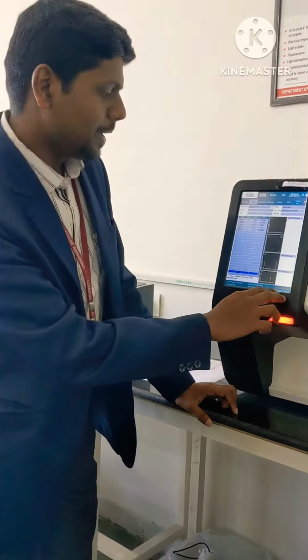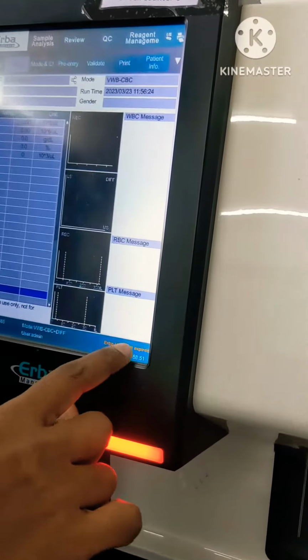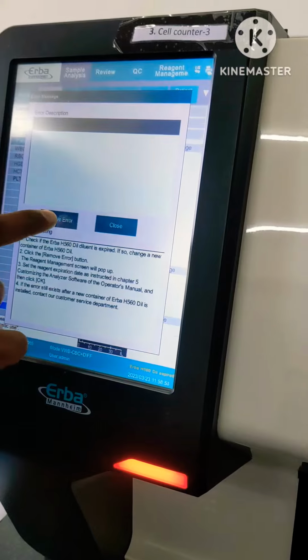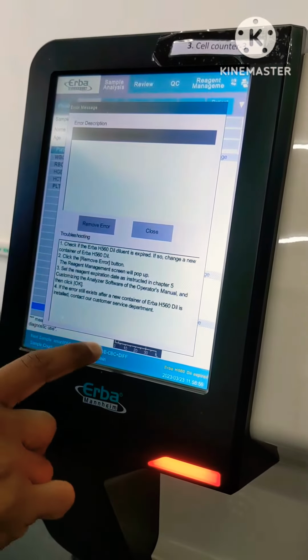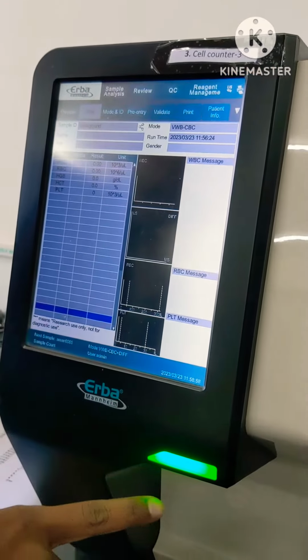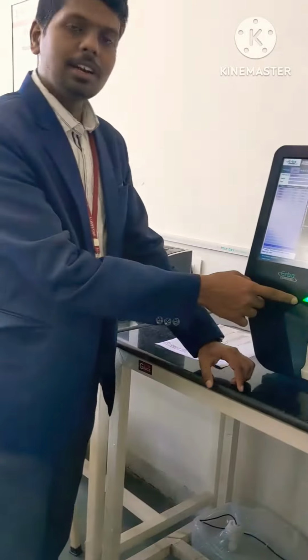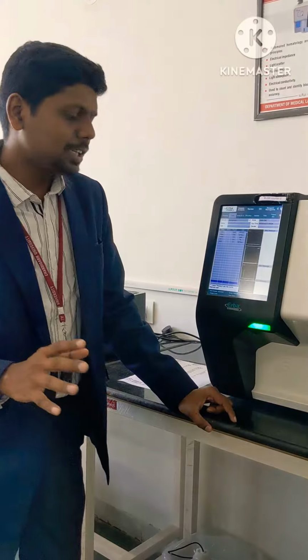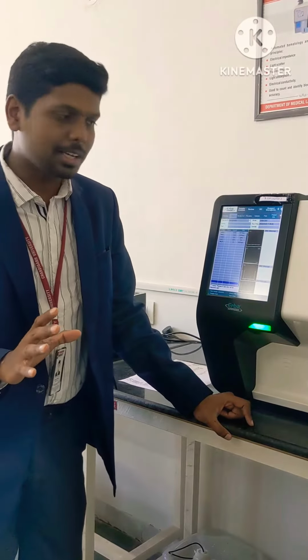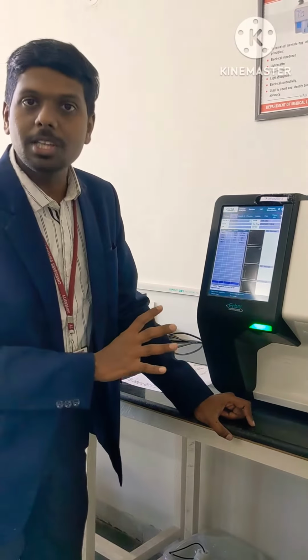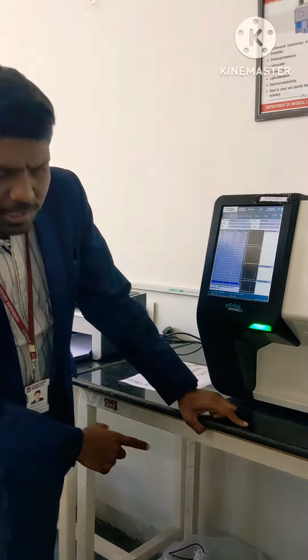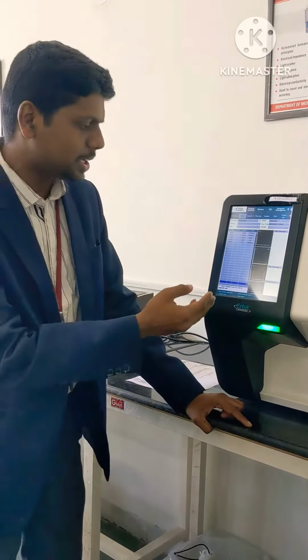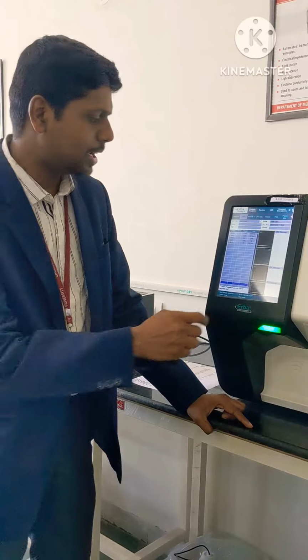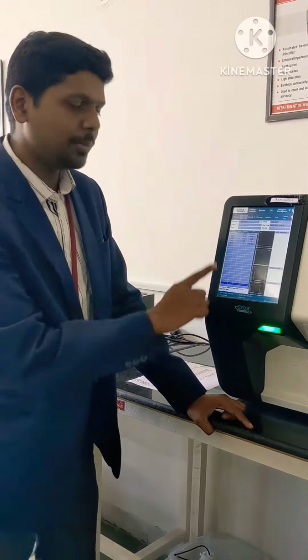So come closer. So here you just click this error code, then you click remove error. So once you click remove error, the error will be removed and it will turn green. So green color indicates that the machine is ready for running the tests. Okay, so in actual labs we are not supposed to do it, but this is the protocol of removing the error. Sometimes there might be some sensor issues or some other things that can result in this error code, and we can easily rectify the error by going to this option and removing the error code.